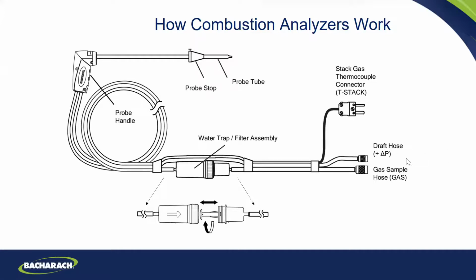You have a pump in your unit here, and the pump is going to be pulling a sample of gases around this thermocouple. The thermocouple is going to be reading temperature. That thermocouple wire goes around here, goes up here, and comes in this plug. You plug it into your instrument. The pump in your unit pulls the gases from this hollow tube through this hose, through the water trap, which drops out the water, through a filter, which picks up the particulates, and into your unit for your gas sample. If it's an Insight Plus, you also have a separate draft reading, because your draft sensor is separate there.